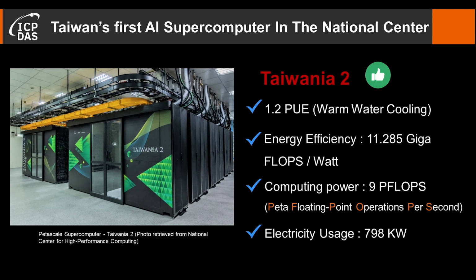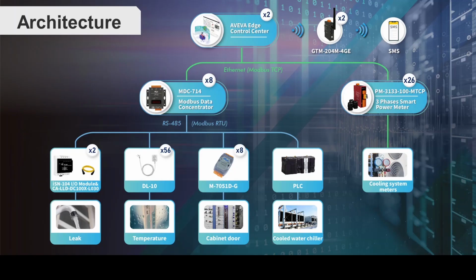That's why the client wants to do the environmental monitoring, because just one environmental factor exceeding thresholds at the national center is enough to cause equipment failure. ICP DAS provides a tailored environmental monitoring solution. In this case, the client uses leakage monitoring modules, which consist of the ISN104 module and the leakage detection cable to monitor the leakage conditions. Once leakage is detected, the ISN104 module will send the leakage information collected from the detection cable to the MDC 714 via Modbus RTU.